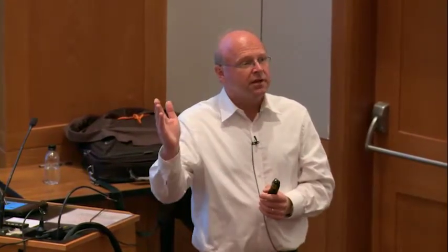For the in-plane resolution, it depends now on your imaging system. And that depends, again, on your working distance. It depends on your lens. And it depends, of course, as well on your discretization at the camera side. So many aspects coming together. And you could say that with a typical working distance, you have restrictions in the same order of magnitude. Let's say 20 microns are maybe resolvable in the visible, without an intensifier. If you have an intensifier, it's worse. Answered? Yes. Okay.